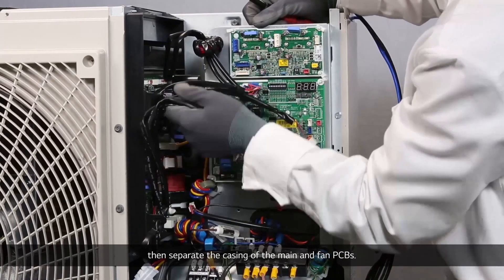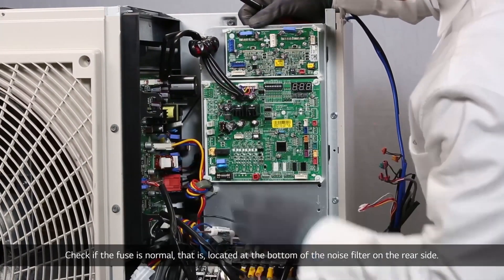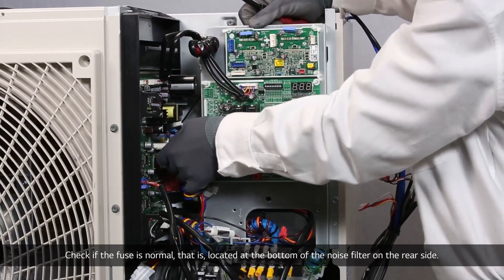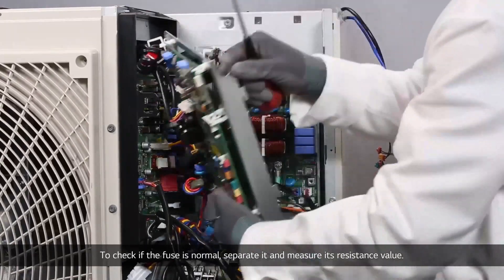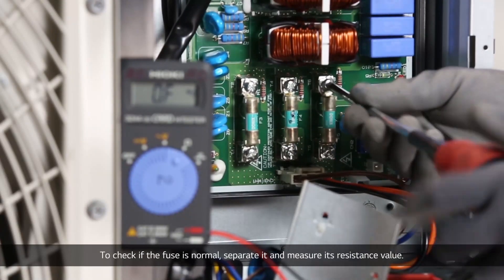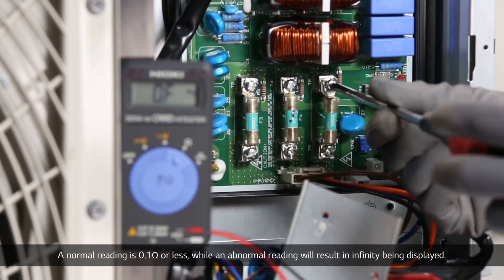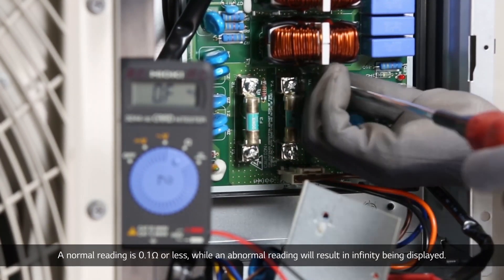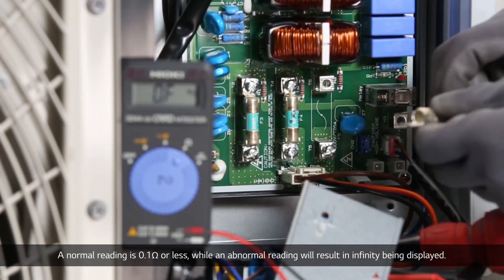Check if the fuse is normal that is located at the bottom of the noise filter on the rear side. To check if the fuse is normal, separate it and measure its resistance value. A normal reading is 0.1 ohm or less, while an abnormal reading will result in infinity being displayed.